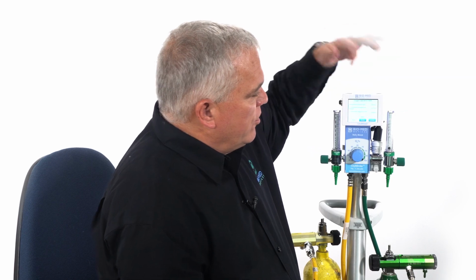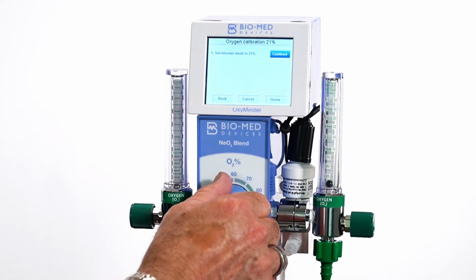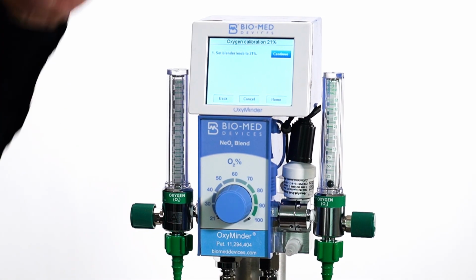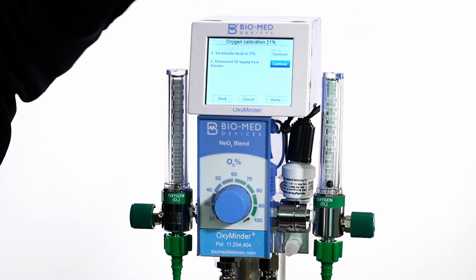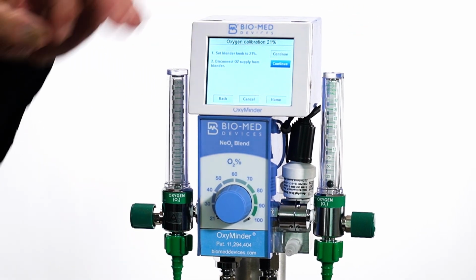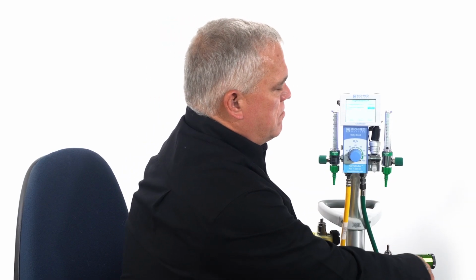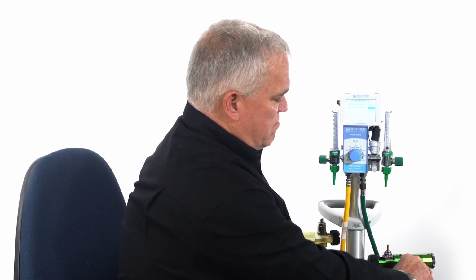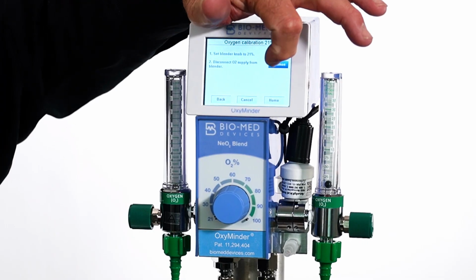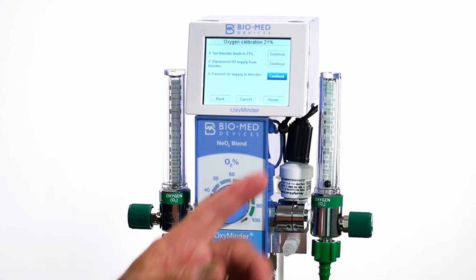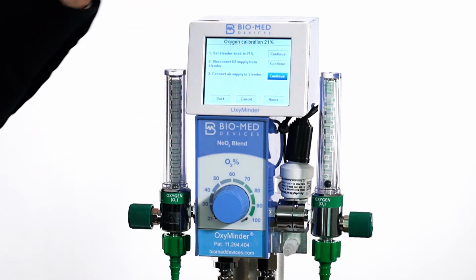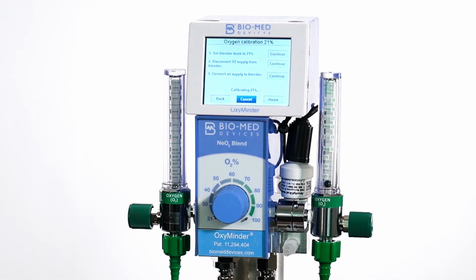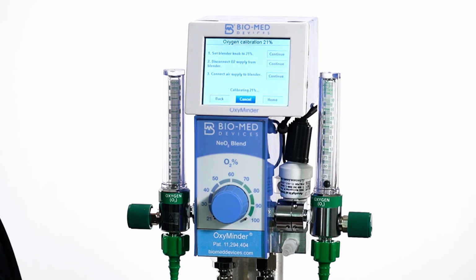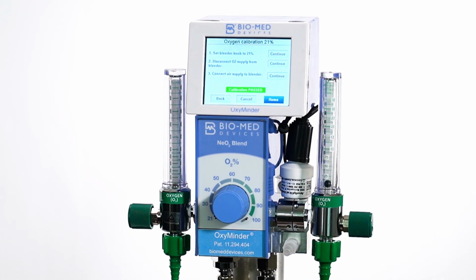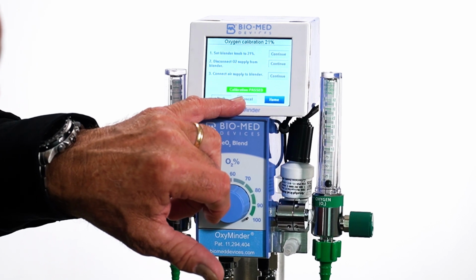If I push continue, set blender to 21% and continue. Disconnect O2 supply. And continue. Connect the air supply. I'm connected, so I'll push continue. Now we're doing our 21% cal. And we are calibration passed. Little green bar.